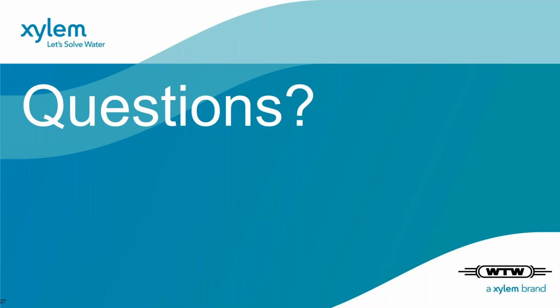The next question concerns the data. Can the data be mapped directly to a cloud? There is an option for IQ SensorNet: we have the IQ Web Connect, and we also have controllers with Ethernet connections, so you can connect Ethernet or a modem on your own, and if you have your internal cloud or for governmental reasons, you can connect it to that. We also have other field buses available: Profinet, Ethernet IP, Modbus TCP/IP, or the regular ones if required.